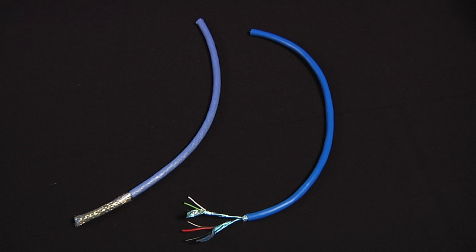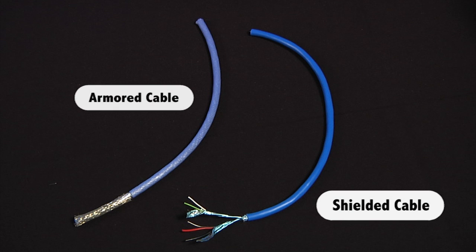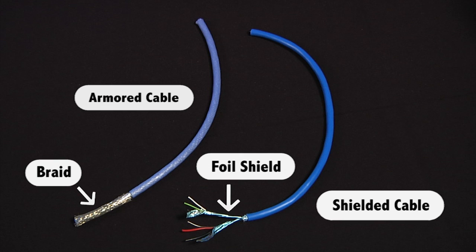When assembling cable glands for Micromotion devices, you must use either shielded cable or armored cable with a cable gland. Unshielded cable has to be run inside a shielded conduit. Shielded cable is surrounded by a foil shield. An armored cable is surrounded by a braid. In either case, the important thing to remember is that the foil or the braid should be terminated inside the gland and not inside the wiring compartment.